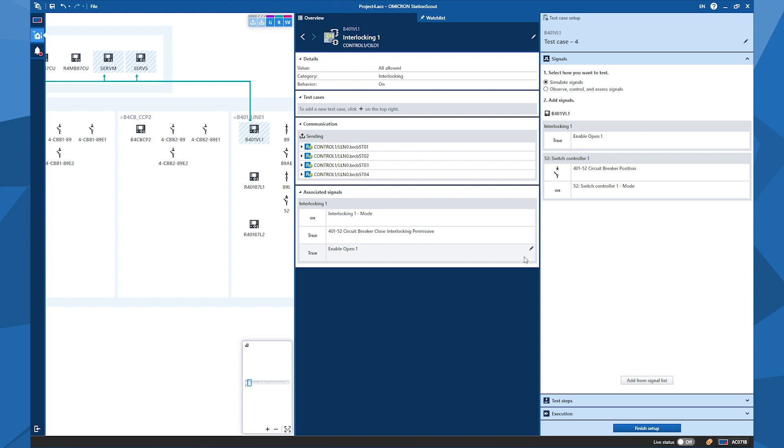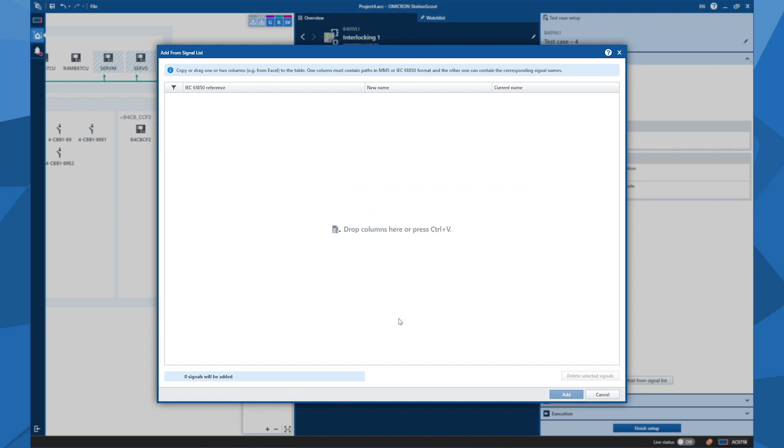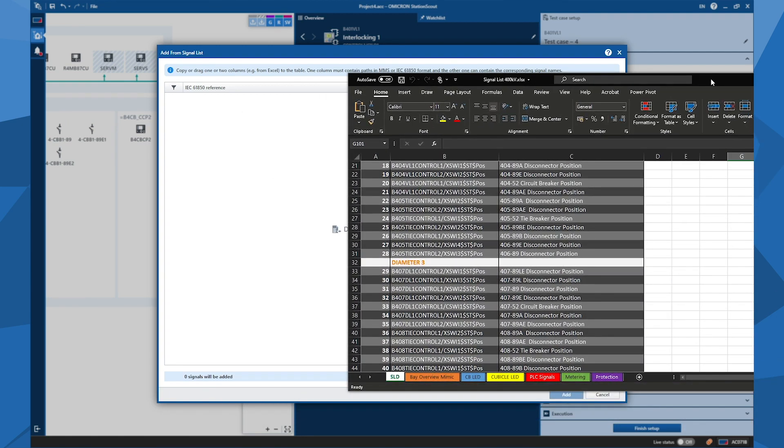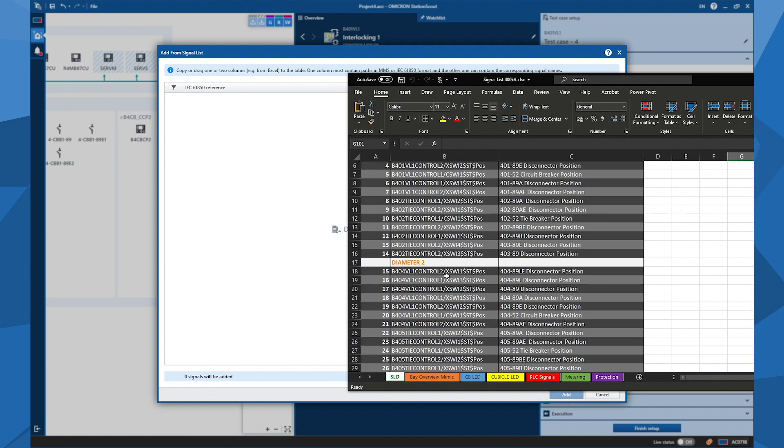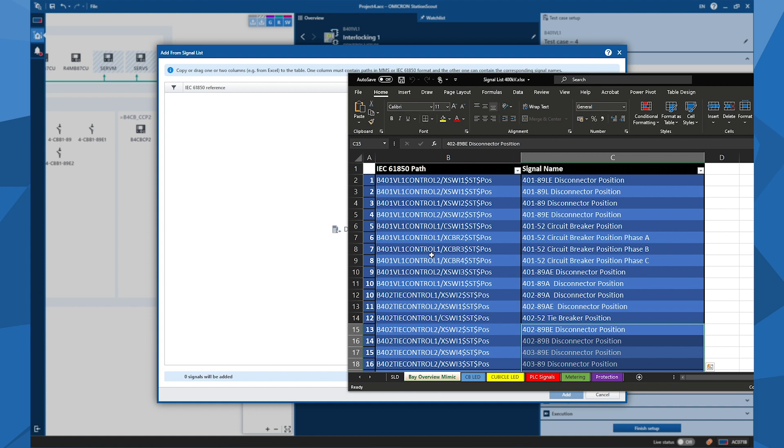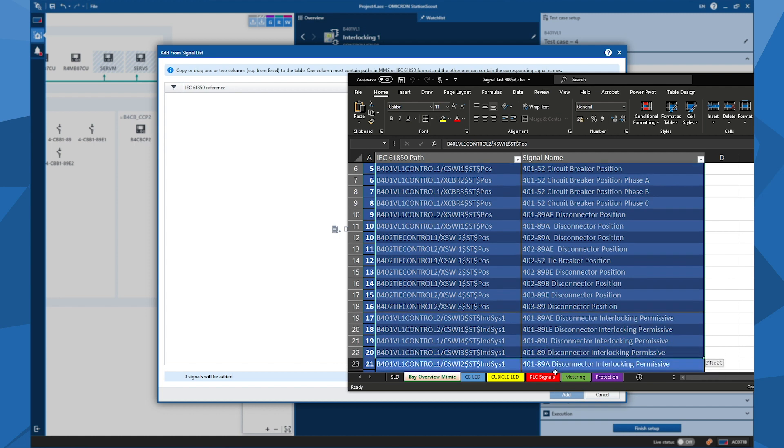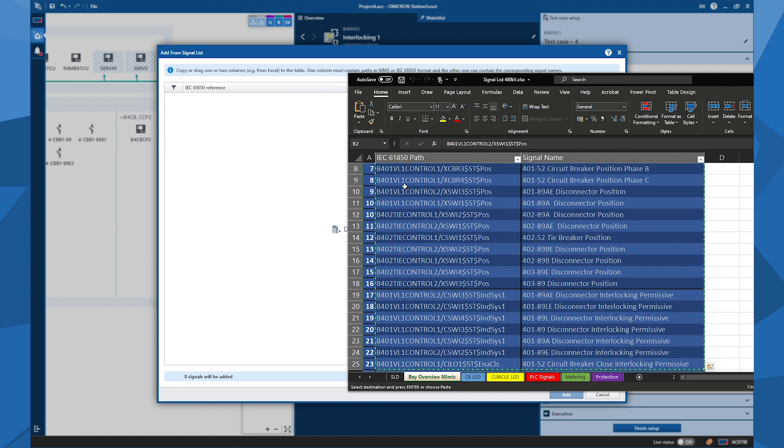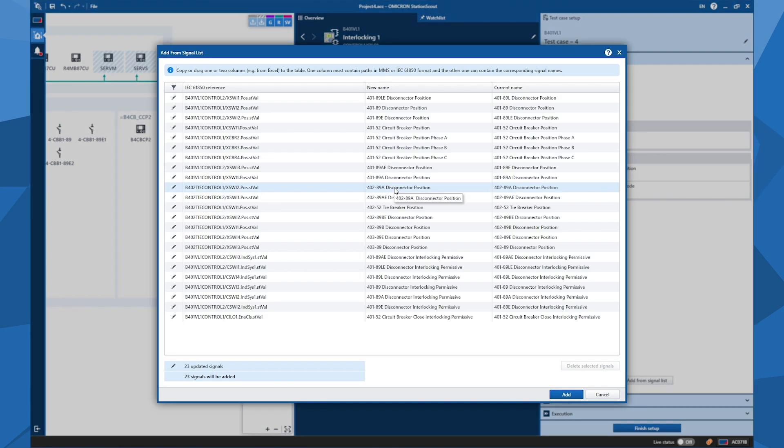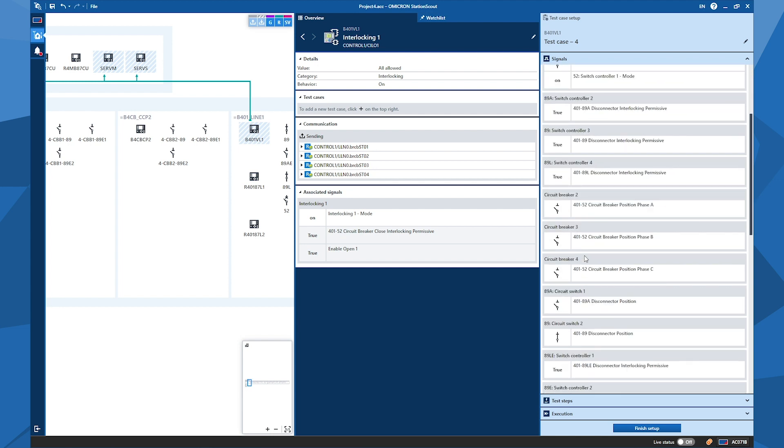And alternatively, I can use add from signal list button to add signals from a signal list. To do so, I click on it, and now I switch to my signal list. So in my signal list here, which contains 61850 addresses and the names of the signals, that means I can also take the signal names in the local language to visualize them with my custom names in the Station Scout project, and then I see the names become clearer. So if I click on some signals like this, copy it and then paste it to here and click on add, and now the signals appeared here.